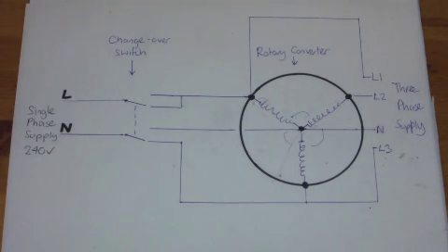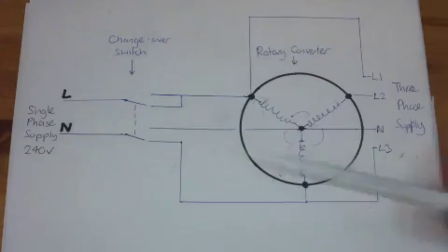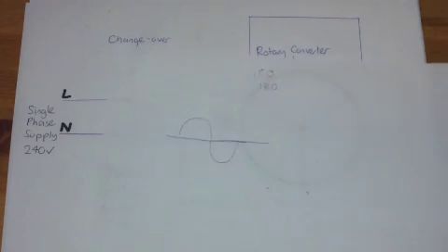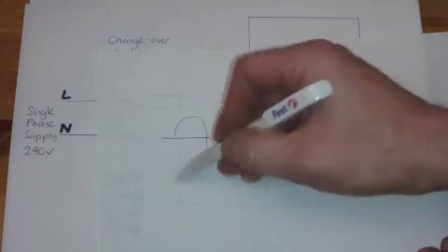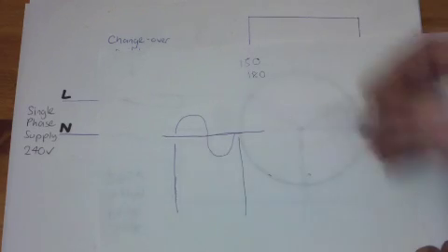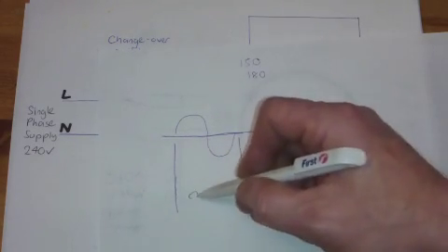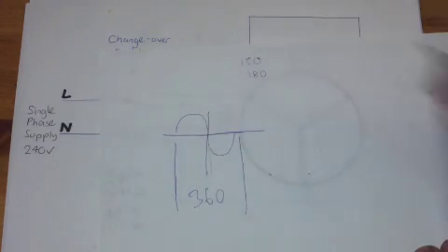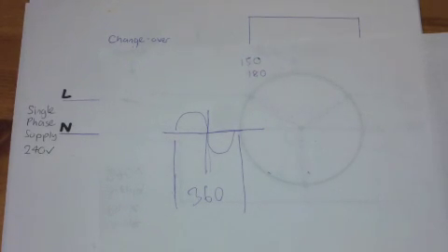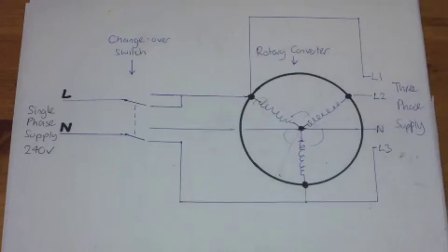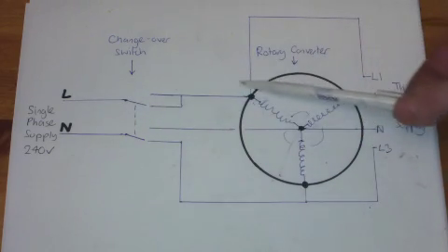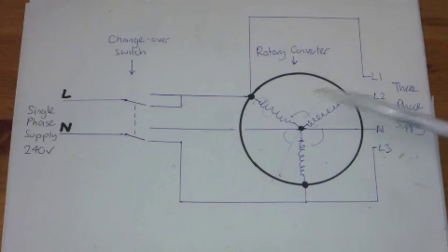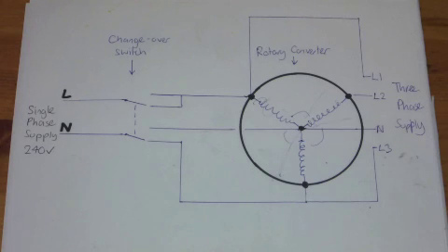So why is this converter so much more efficient than everybody says of rotary converters. If we go back to where it all starts for us it starts at 240 volt single phase supply. There's a sine wave representing a 240 volt supply and that sine wave represents one rotation of the electrical machine that made it and one rotation is 360 degrees therefore it follows at the halfway point is half of that 180 degrees. Looking at our three phase machine each of these are 120 degrees apart so this little supply that's coming along here that's spaced at 180 degrees apart we're shoving down two wires that are actually 120 degrees apart.